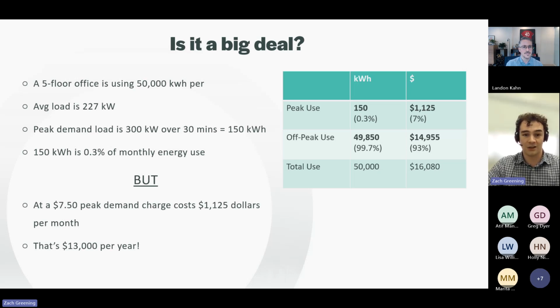In the case of this building, using an average of 50,000 kilowatt hours over the course of a month, only 150 kilowatt hours, just 0.3%, was used during their peak period. But look at that cost: that 0.3% of energy made up a total of $1,125 of the bill, 7% of their electricity costs for 0.3% of their energy use.